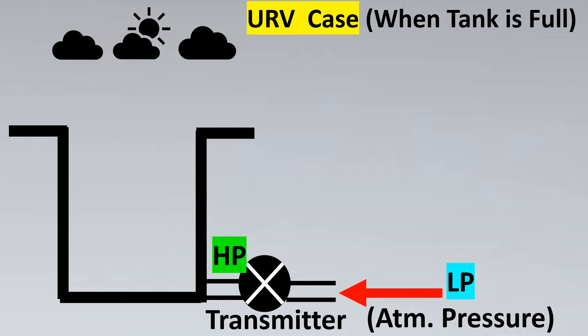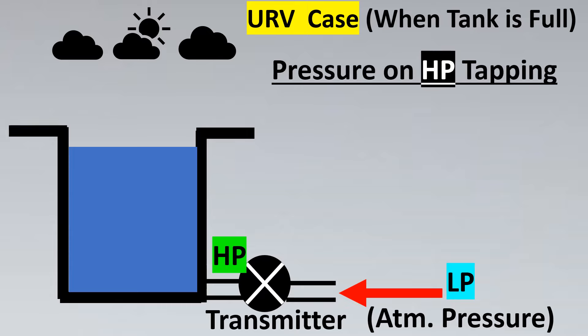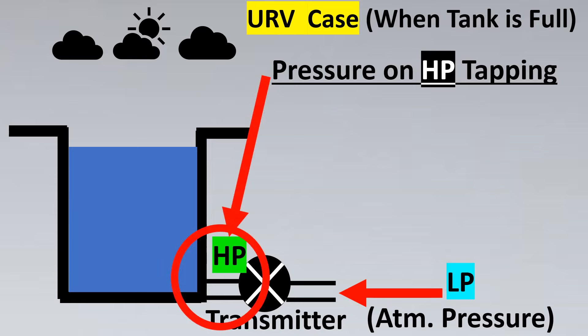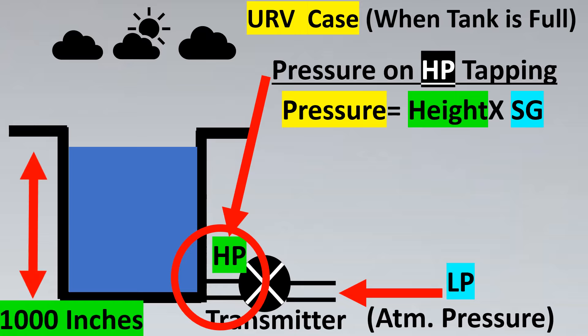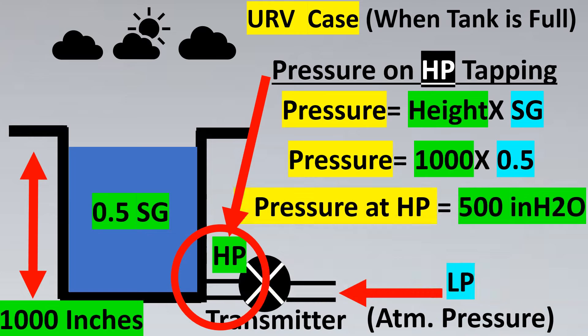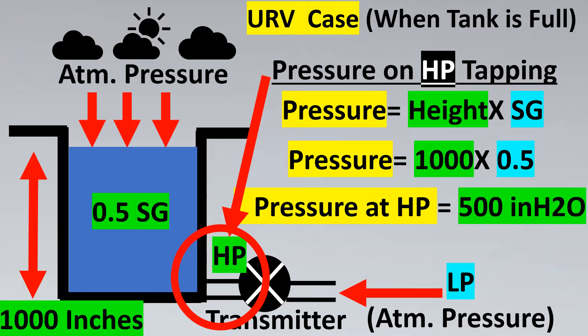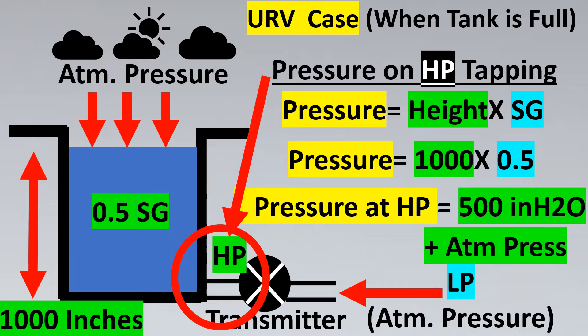Now let's look at the URV case when the tank is full. We need to calculate the pressure at the HP tapping using the equation: pressure = height × specific gravity. The C-to-C distance is 1000 inches and the specific gravity of the liquid is 0.5, giving 1000 × 0.5 = 500 inches of H2O. Since the tank is open, atmospheric pressure also acts on it, so the pressure at the HP side is 500 inches of H2O plus atmospheric pressure.